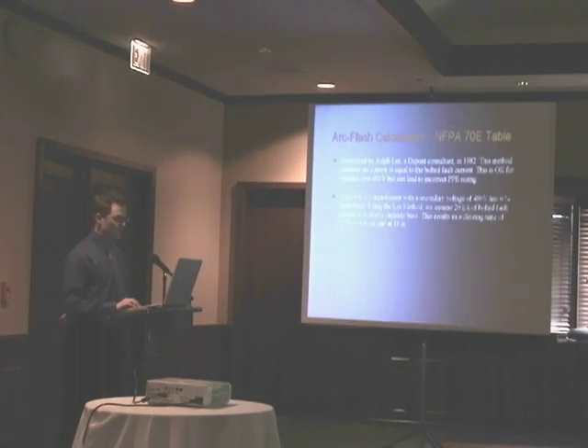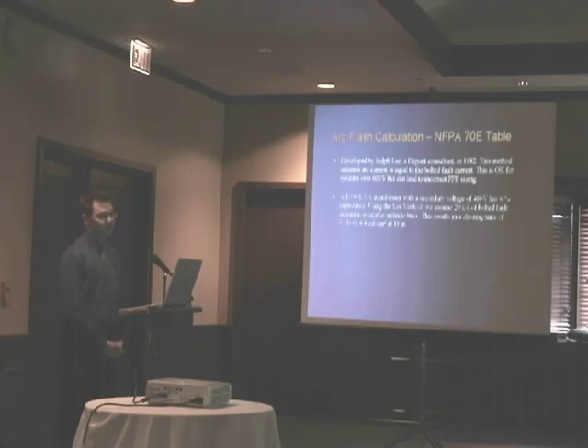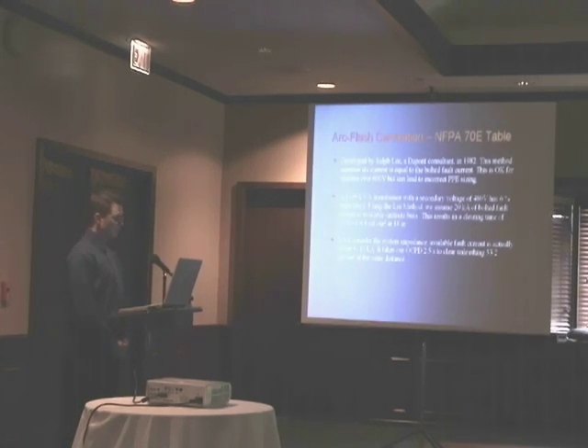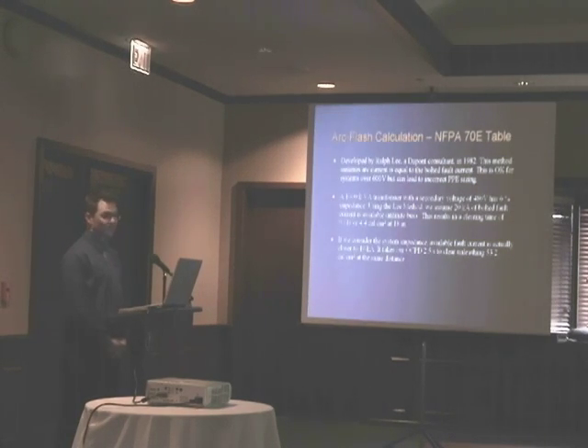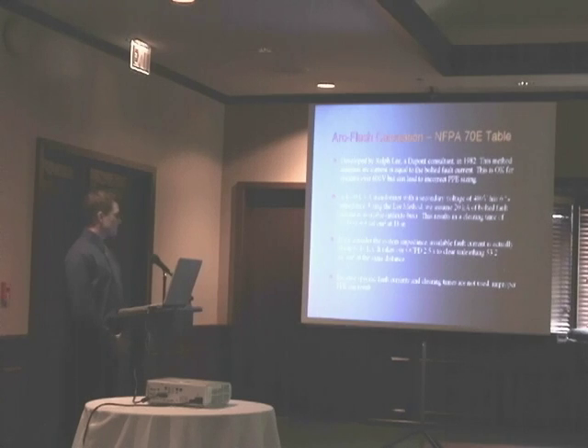A 1000 kVA transformer with a secondary voltage of 480 has a 6% impedance using the Lee method. We assume 20 kA of bolted fault current is available. This is assuming an infinite bus. This results in a clearing time of 0.11 seconds or 4.4 calories per centimeter squared at 18 inches. If we consider the system's impedance, available fault current is actually closer to 10 kA. It takes our OCPD 2.5 seconds to clear, unleashing 53.2 calories per centimeter squared at the same distance. Because specific fault currents and clearing times are not used, improper PPE can result, as you can see from those two examples.